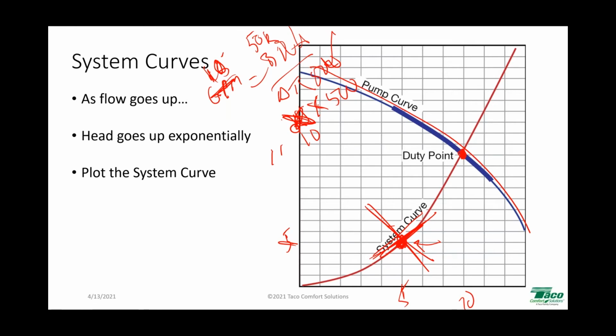It's so common. And the thing about it is, guys will say, well, I've been doing it this way forever and I've never had a problem. So I don't know what you're talking about. Well, we have to define what we mean by problem. If you define problem as, well, the system doesn't work, we're not delivering heat, people are mad, they're freezing to death and blaming me, well, no, you don't have a problem. You absolutely don't have a problem. Are you going to be able to deliver 50,000 BTUs as needed with 10 gallons per minute? Well, yeah, you can do that all day long and twice on Sunday.